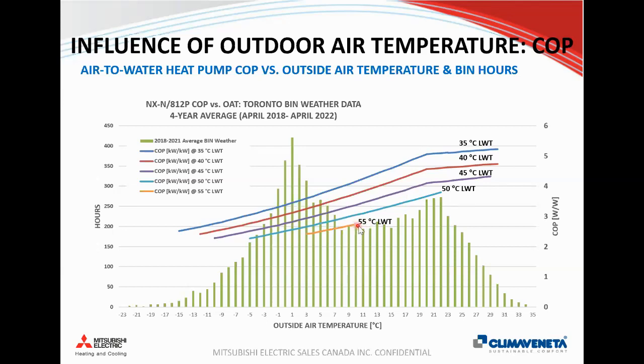We looked at the operating envelope before, saying these machines could give you 55C. You see that, comparatively, this is the lower COP. We're at about 2.5, but it's also starting at 3 and ending at 10. So that's telling us our operating limits. By choosing a lower design temperature, we can keep the heat pump running for more of the time and also increase the efficiency.